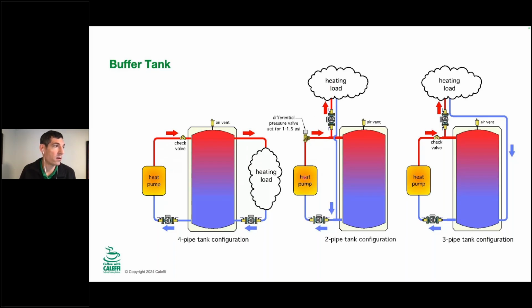So this 140 degrees from the heat pump can go right out to a radiator or to the radiant heating or something like that. It doesn't have to interact with the buffer tank. So in this 2-pipe configuration, we could have all the zones come on, 140 degrees comes out, whatever comes back, and we just do that. We basically haven't engaged the buffer tank at all.